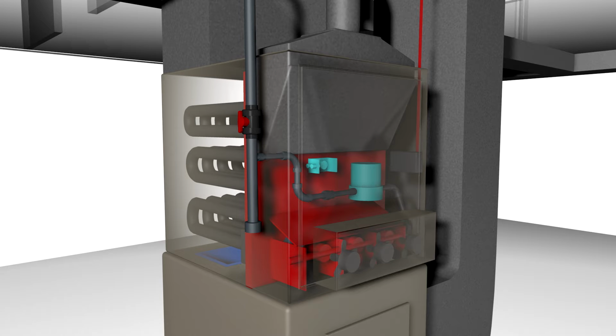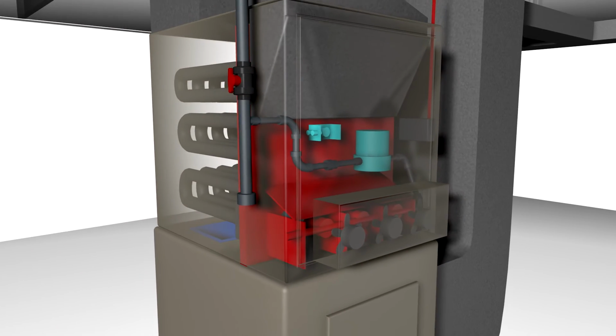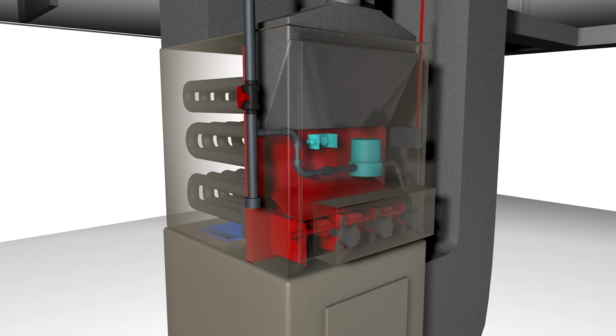Depending on the age or model of your unit, you may have a pilot light, a small gas-powered flame that stays constantly lit to ignite the burners on demand, or you may have an electronic ignition system. The flame sensor is a safeguard that shuts off the gas if the burners, for some reason, do not ignite.